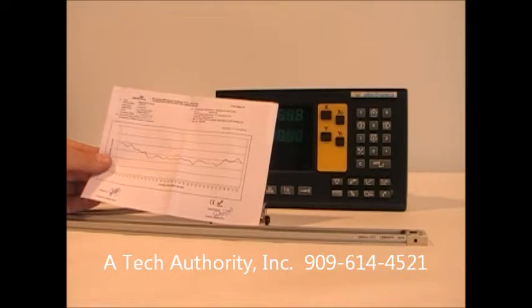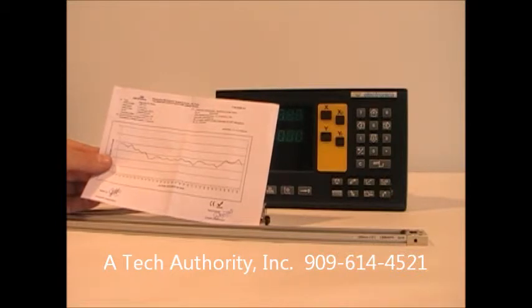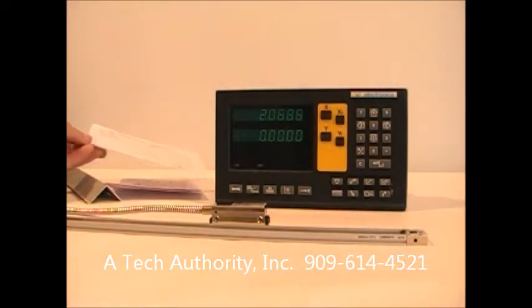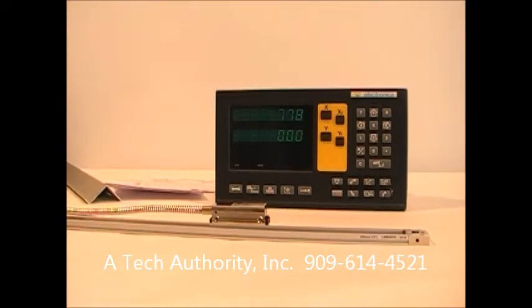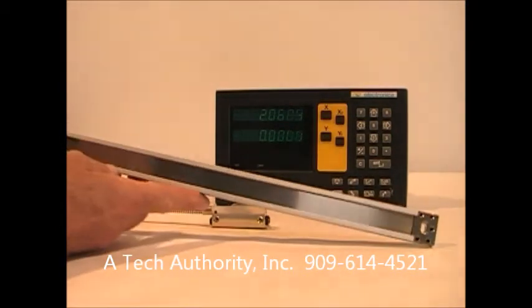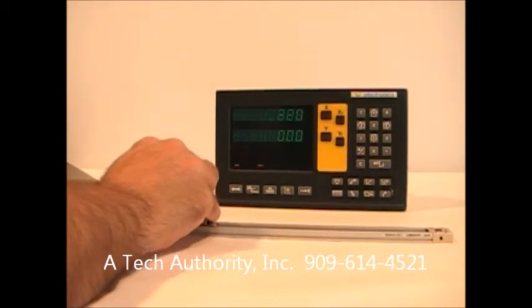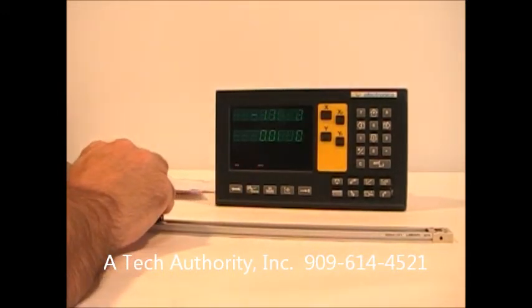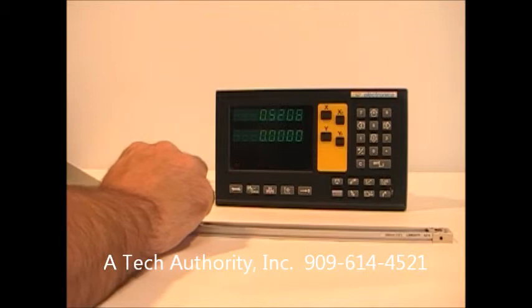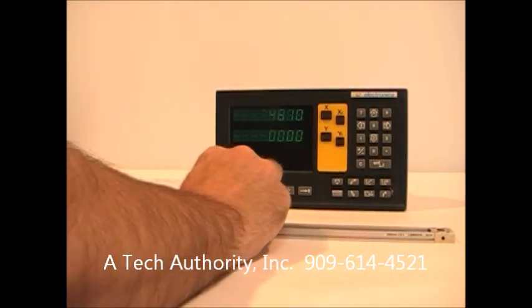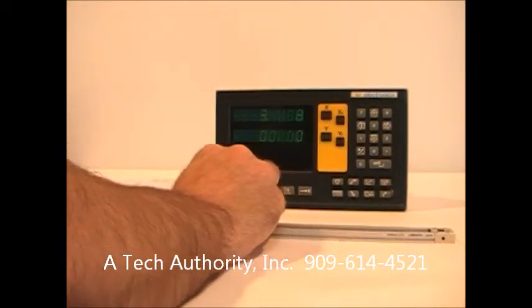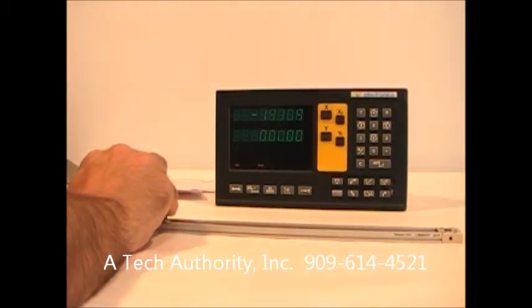Electronica says that their accuracy class of these scales is plus or minus 10 microns per meter. The resolution is, based on a TTL output, 5 micron. And as you can see, the display counts out four places to the right of the decimal. You can get some higher resolution scales, but standard packages are 5 microns.